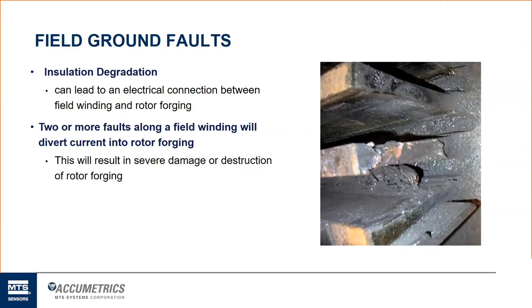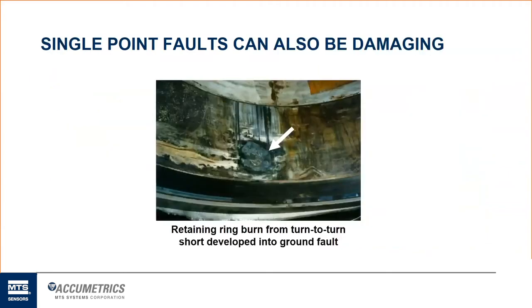It's not always true that two points of a ground fault are what customers are most concerned with. You can have a single point failure. And the next slide shows an example. This is the retaining ring that covers those field windings that come out of each side of the rotor, where you saw them all stacked up in the previous slide. And this was from a single turn-to-turn short that developed in that and caused burning into the retaining ring that needed to be repaired.